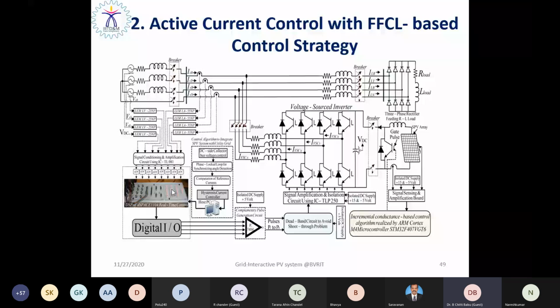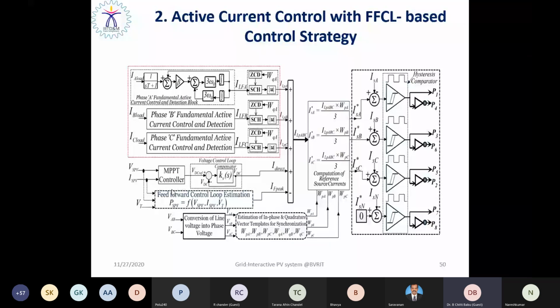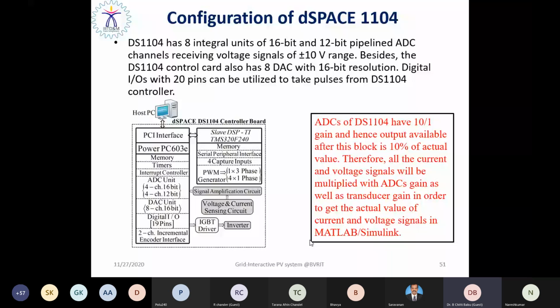And here, in the active current control strategy we made, the feed forward control loop can exactly detect the active harmonic component, so that the control strategy is very accurate for the reference current generation. So this is the way we made this control strategy, called the active current harmonic control strategy, for each phase. And this is one of the very novel and advanced control techniques we have proposed, and that has been published in IEEE Transactions. And this is the configuration of dSPACE. As you might know, it is like a microcontroller with a signal processor, and that has been made in this experimental platform.